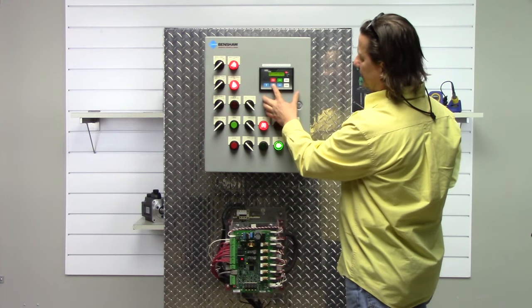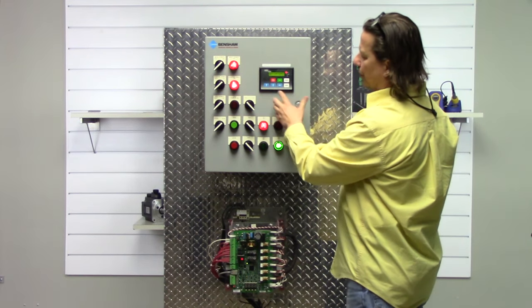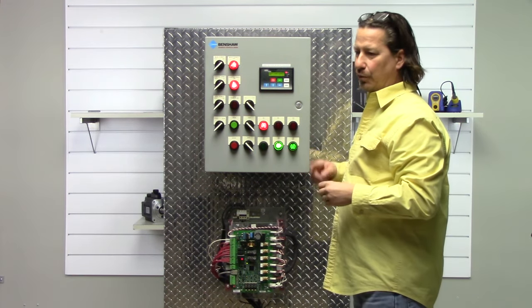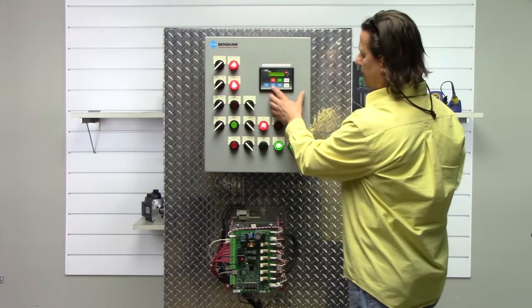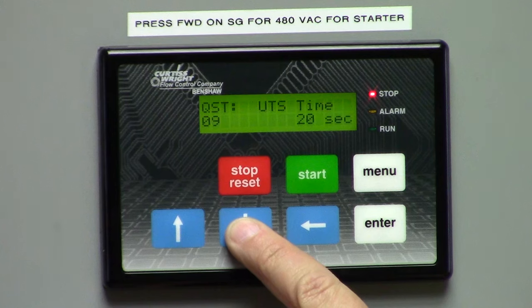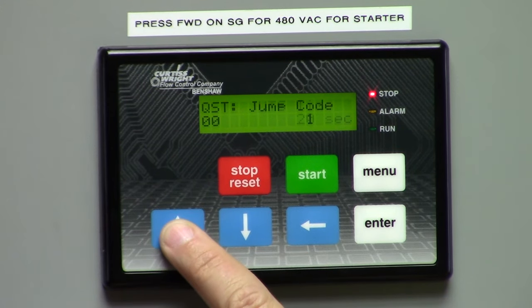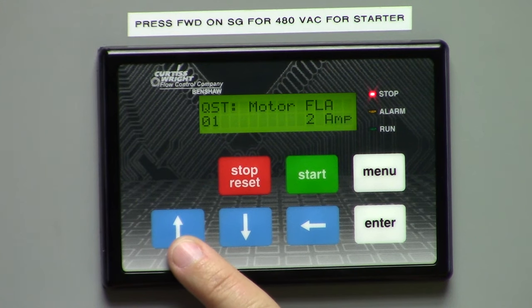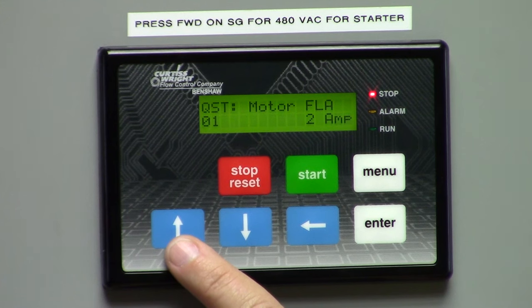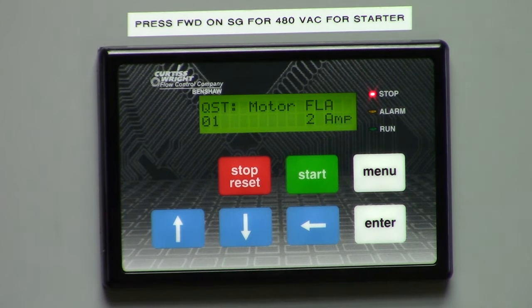You can hit the down arrow or up arrow. If you keep pushing one arrow, it's going to go around in a loop — you can't get lost. The first thing you come to is motor FLA. This is the information you would pull right off of the motor nameplate that this starter is connected to, and this is where you would program it. Right now, for example, we have 2 amps programmed into it.